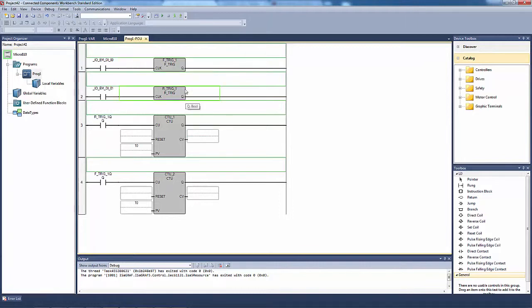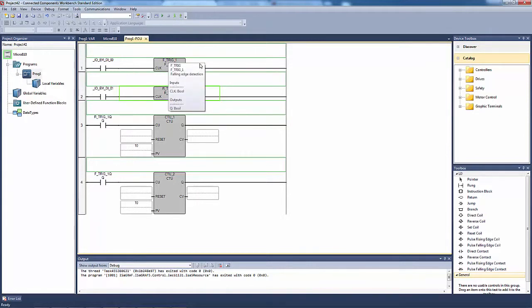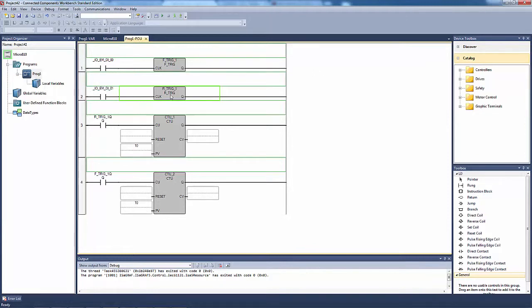What F_trig and R_trig do is every time they get an input, they send out a pulse. Falling edge means when the input goes away, then it sends one pulse. Rising edge means once it gets the input, it sends the pulse. So this waits till it's de-energized, while this one sends a pulse as soon as it's energized.